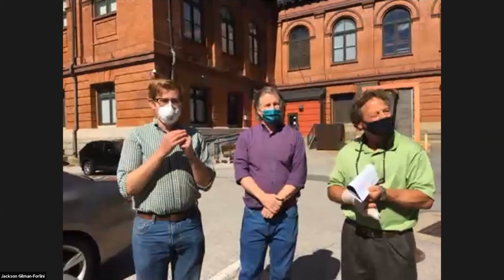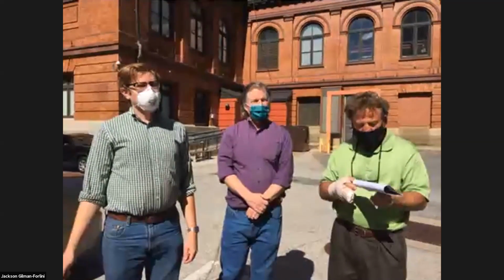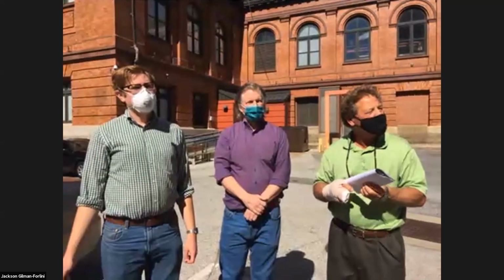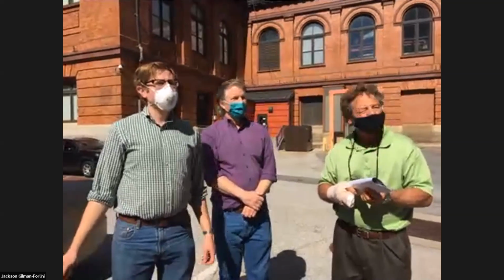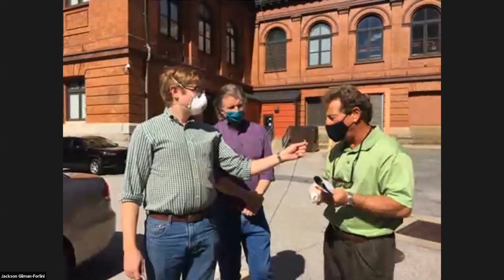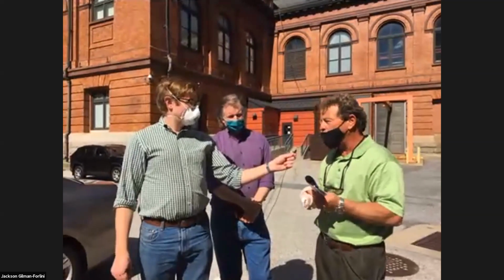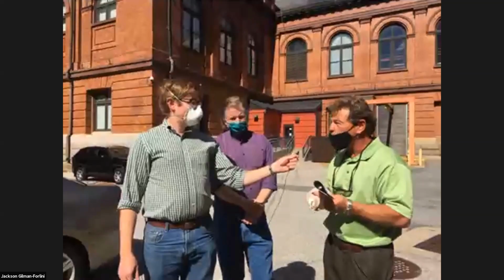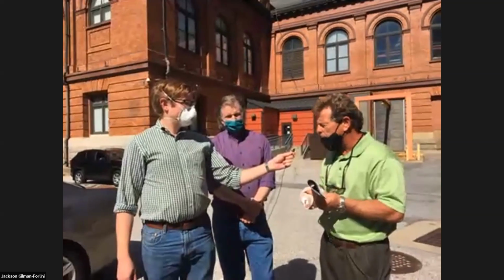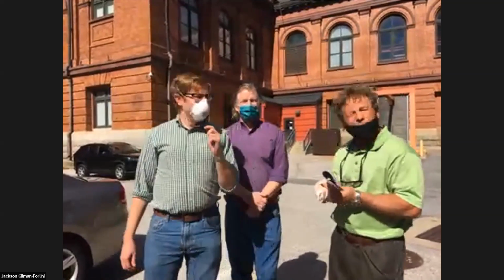All right, how about another question? We've got an engineering question here. What are the current pump sizes and are they variable frequency drives? Currently, these pumps are across the line, solid standard size motors. These are not VFDs. In the new capital improvement project, the city is exploring the idea of moving to VFDs. There are 5 pumps here, and they range in size from 25 to 40 MGD. Thank you.